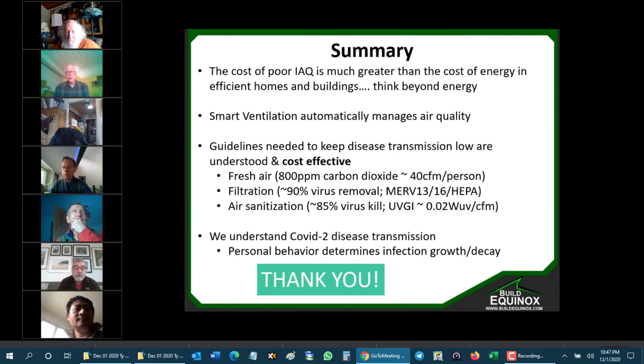But when you do have that outdoor situation, in addition to, say, the MERV 13 filter, you can also add a carbon impregnated filter that we have. If there's odor coming in because of that outdoor fire, that will absorb that part of it as well. We haven't put the algorithms in yet, but the CERV-2 is set up so you can have both inside and outside CO2 and VOC measurements.